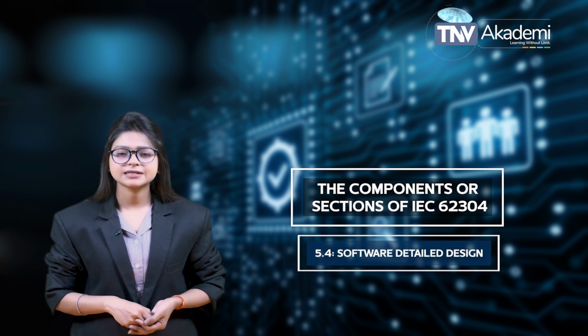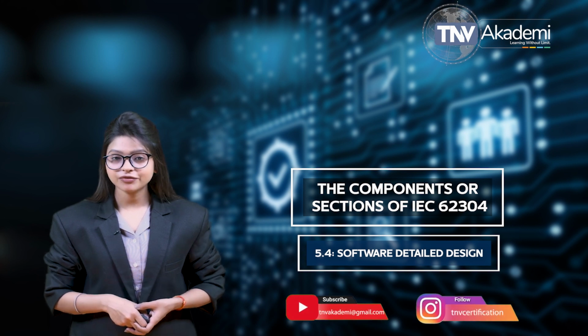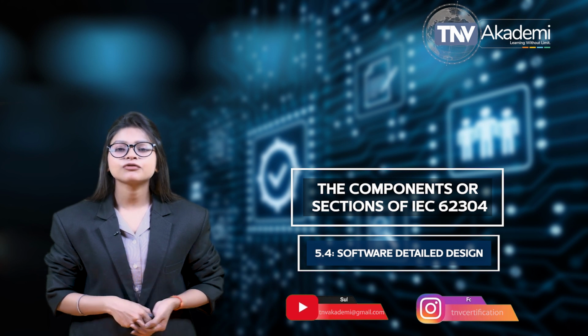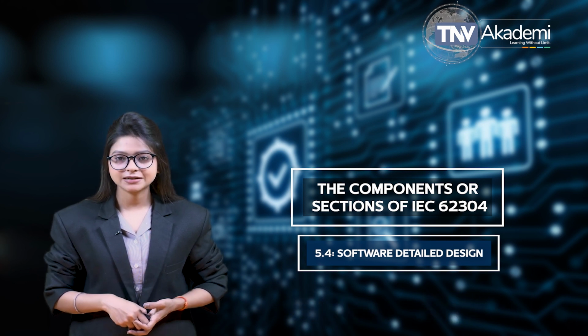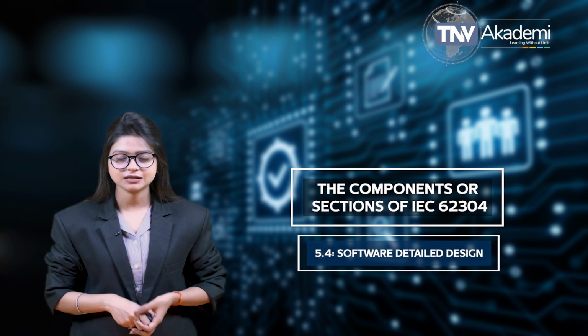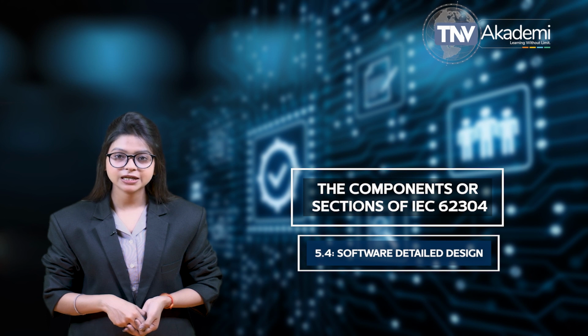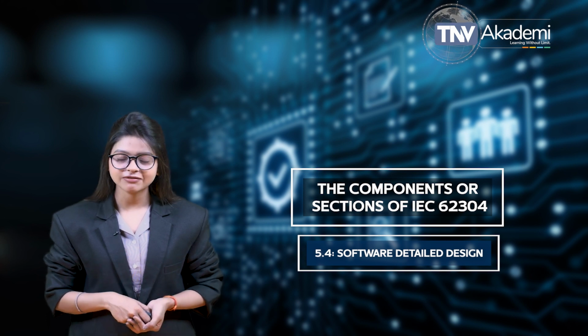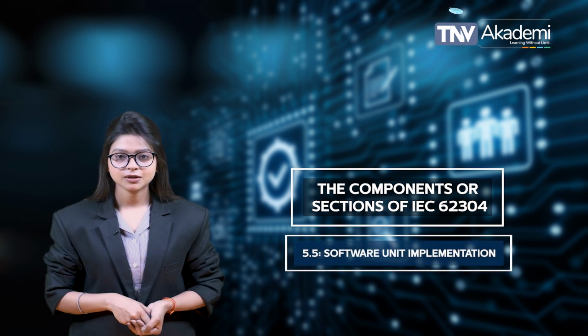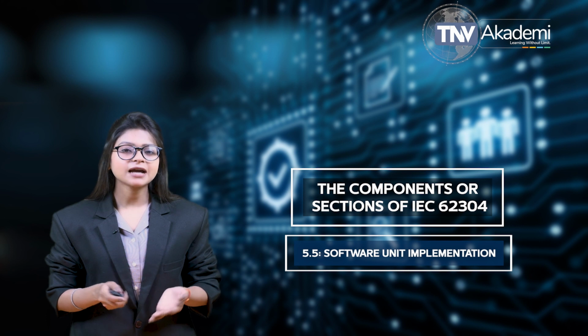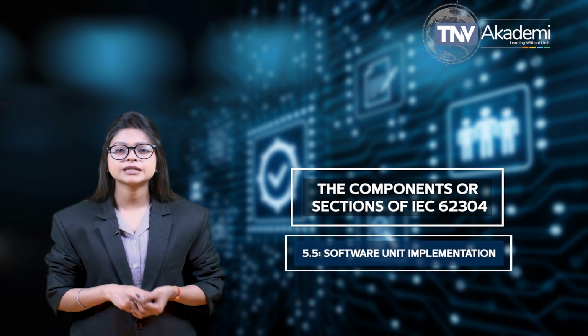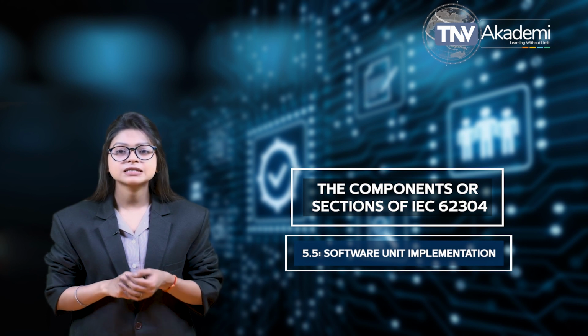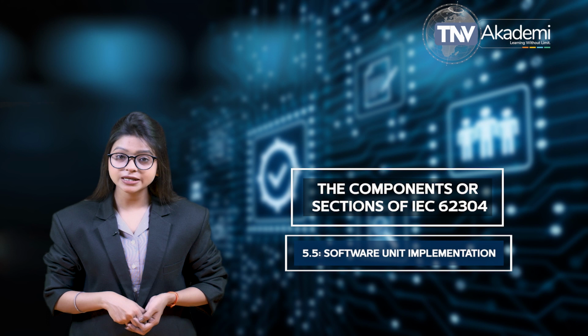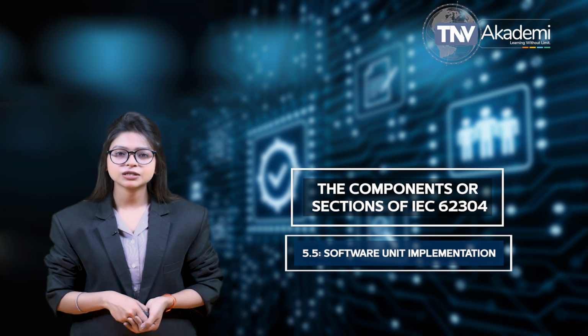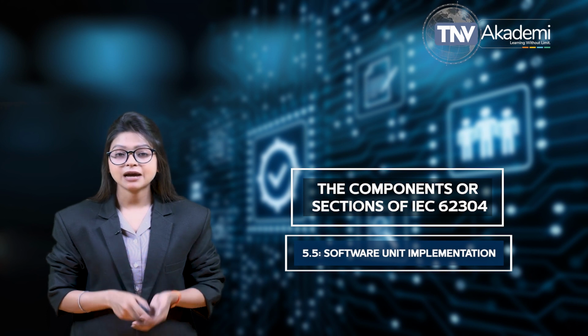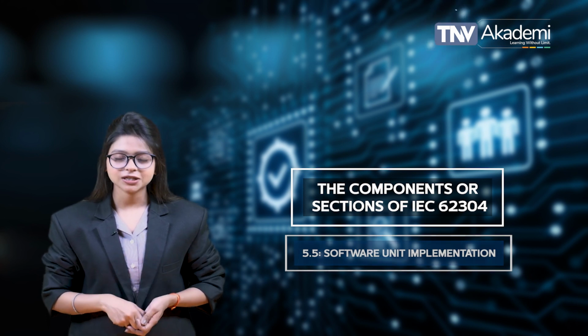5.4. Software detailed design. This subclause specifies that the manufacturer will subdivide the software into software units and document and verify a detailed design of each software unit and interfaces. This is to be done with sufficient detail to enable correct implementation of the medical device software. 5.5. Software unit implementation. This can be thought of as a software coding phase or building phase, where the prior subclauses were serving to establish the blueprint of what is to be coded or built. These subclauses must include verification for the valid software units and must specify verification acceptance criteria.